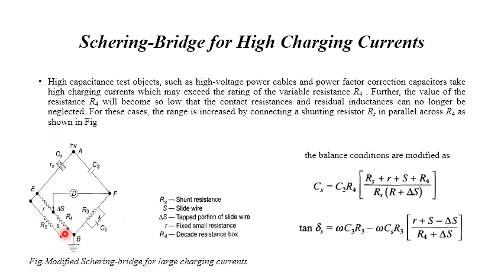the resistance R4 will become so low that the contact resistance and the residual inductance can no longer be neglected. This means that because it is subjected to high current, there is also an inductance, the residual inductance, which also comes into the picture. So for these conditions, the range can be increased by connecting the value of RS, which you can see here in parallel with the R4. So this is for objects like power cables and high charging current devices.